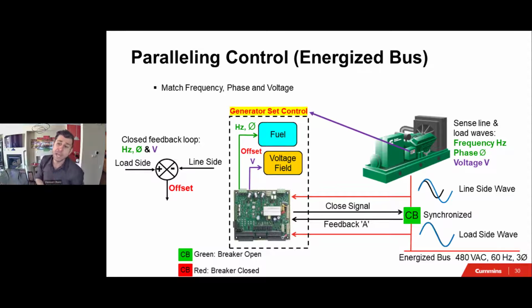And once the sync conditions are met, we'll send a signal to the circuit breaker. And by the way, we need to see that breaker close within 5 cycles. Otherwise, we will lose that synchronization. We won't be able to close, and we won't be able to bring the two together. So we want to close within 5 cycles. This is very typical of all paralleling breakers, regardless of the manufacturer, whether it's ABB, Schneider Electric, or others.